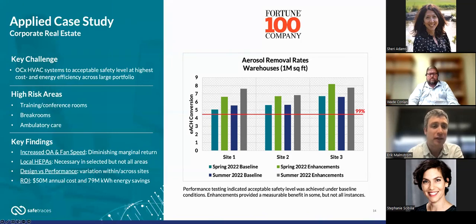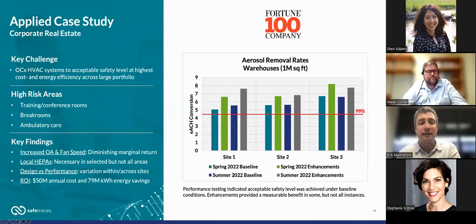That helped guide where they were going to use local HEPAs. Finally, like many commissioning studies, we found that where facilities should be performing on paper versus actual performance were often highly variable, both within a location and across sites—things that on paper should perform at a certain level and be similar were often very different. The value of all this data we provided through our testing for this client across their portfolio led to $50 million of annual cost savings and nearly 80 million kilowatt hours of energy savings. So we're talking about real money and real energy savings through our data.